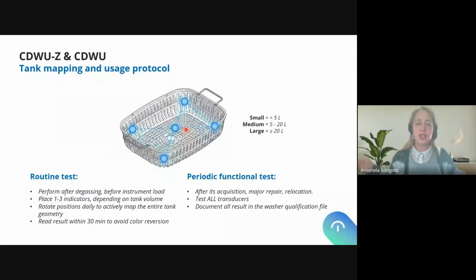So the walls, sorry, the corners, are generally cold spots of cavitation. This is why it is important to test the corners, changing the location of the indicator, in the same way that we should do with cleaning indicators inside thermal disinfector machines, changing location to corroborate that the full machine is working. This is the same concept.